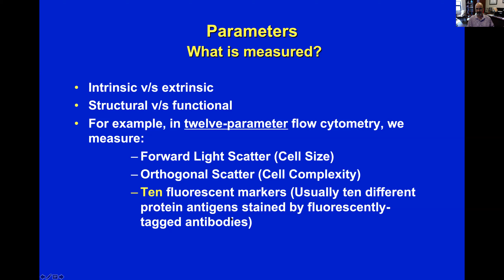How does the chemistry accomplish itself? I'll use a simpler example of a 4-color or 6-parameter machine called the FACSCalibur. This particular machine has 2 lasers. It is still a workhorse in many clinical labs, or even research labs. This argon laser emits light at 488 nanometers, monochromatic light. And it has another laser, the helium neon laser, which emits light around 635 nanometer wavelength, okay?